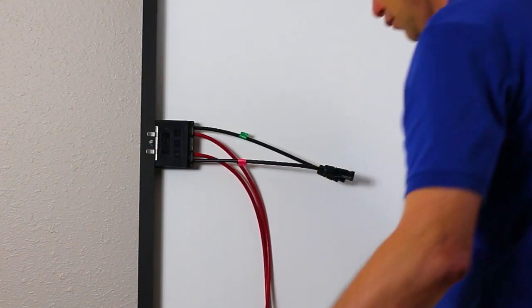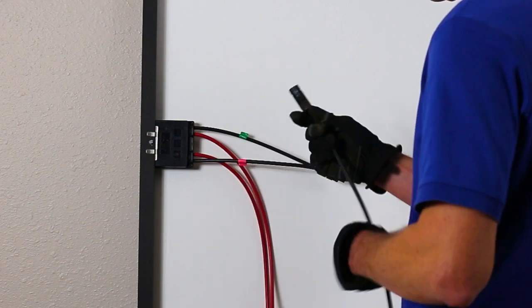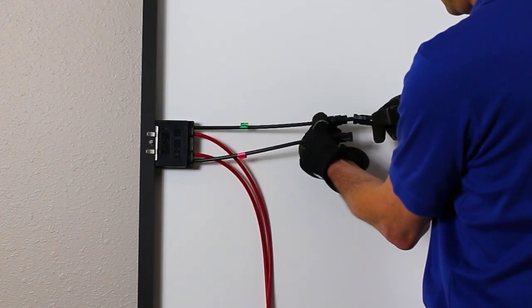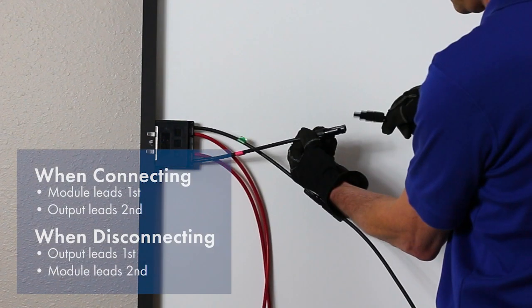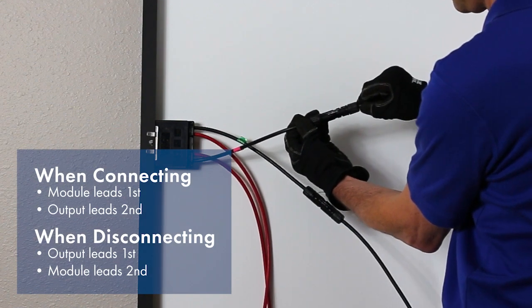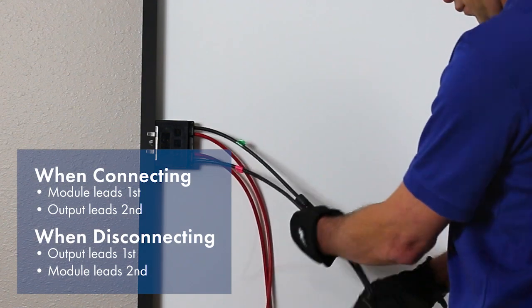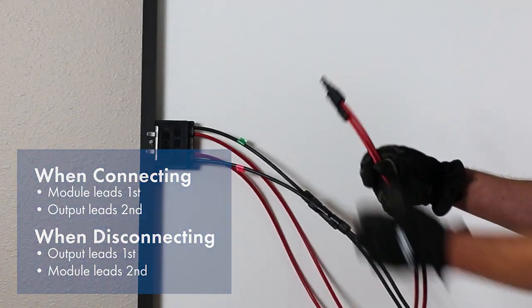Once the receiver is installed, the module junction box leads are attached to the short black JMS input leads. Please note the module connection must be made before the red output leads are connected. If the unit needs to be removed, the output leads must be disconnected first.